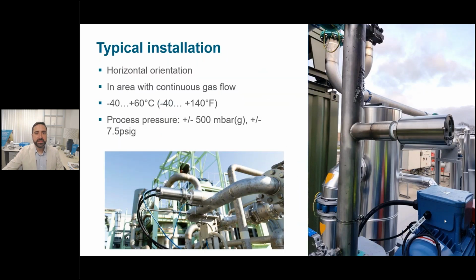See, typical installation for these is pretty simple. Outside in the pipe, wherever you'd like to measure. It's pretty straightforward, like I said, but there are a few things to consider. Given that this is an optical measurement, they are sensitive to temperature and pressure, so there's a fairly limited range for both, so we can deliver the accuracy that we promise. Anywhere below 140 degrees Fahrenheit and 7.5 PSIG is where we're going to perform best. And they also work under vacuum to about 7.5 PSIG as well. Continuous flow and a horizontal orientation is going to be the best way to manage any condensation in that location of the process as well. Next, please.